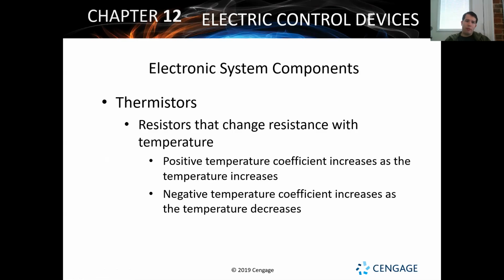So another thing we've got is a thermistor. A thermistor is a pretty simple device, an electronic component that changes resistance based on temperature. Thermistors are used in a lot of different settings. Sometimes they're used as temperature sensors for overheating on a furnace, to turn a system off in case that happens, or for a boiler overheating, to prevent that from happening. That's a typical thing you'll see thermistors used for with heating equipment, used as a safety sometimes. But for controls, we use thermistors in a lot of different ways.